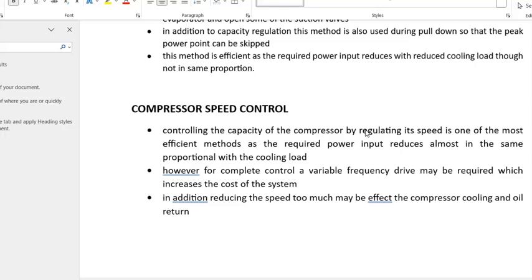However, for complete control, a variable frequency drive may be required, which increases the cost of the system. Here we are using a variable frequency drive motor, which is costly, so it will increase the overall system cost. But it's more efficient because cooling load is directly proportional to the power. In addition, reducing the speed too much may affect the compressor cooling and oil return. If the speed is too low, then oil return is also less, and compressor cooling is also affected.